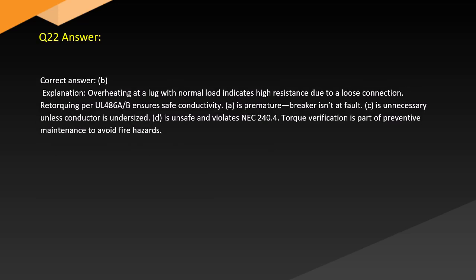Answer. Correct answer: B. Explanation: Overheating at a lug with normal load indicates high resistance due to a loose connection. Retorquing per UL ensures safe conductivity. A is premature; the breaker isn't at fault. C is unnecessary unless the conductor is undersized. D is unsafe and violates NEC 240.4. Torque verification is part of preventive maintenance to avoid fire hazards.